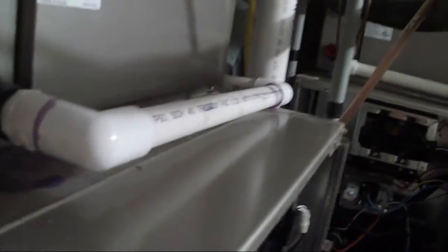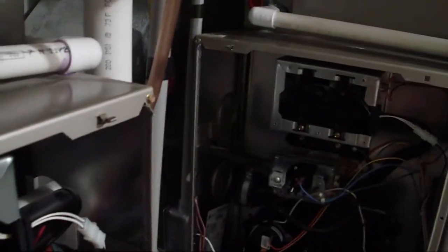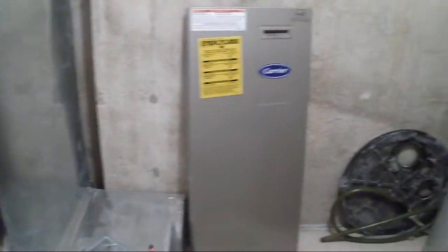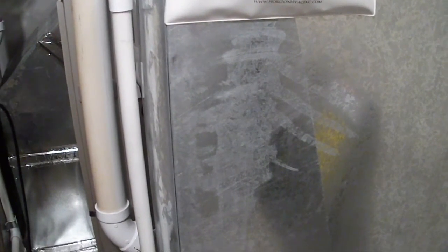So what I do is I put the coil cleaner on. What, like ViperBrite? Well, I usually use the non-acidic one, more like an evaporator coil cleaner. In the summertime we use the condenser cleaner, it's real acidic. But I'll spray it down with the coil cleaner and then I'll put it through defrost. And the defrost naturally rinses the coil. That must be cool. Yeah.